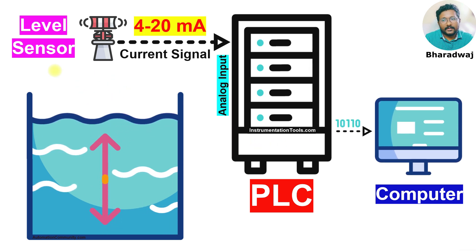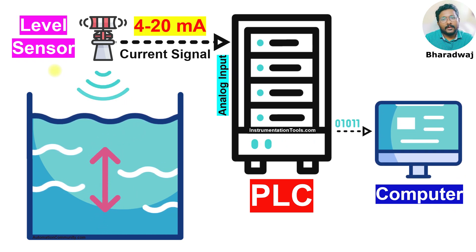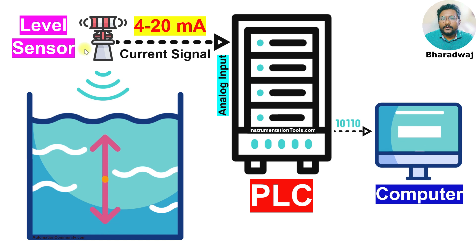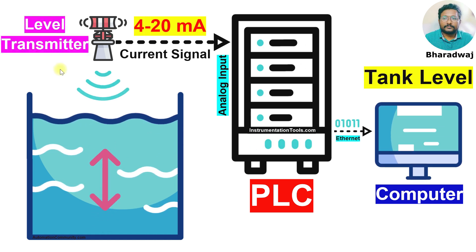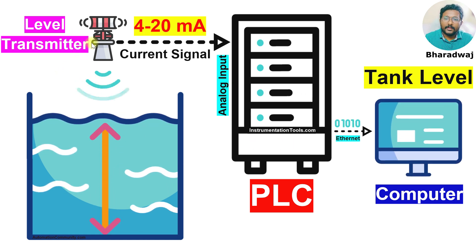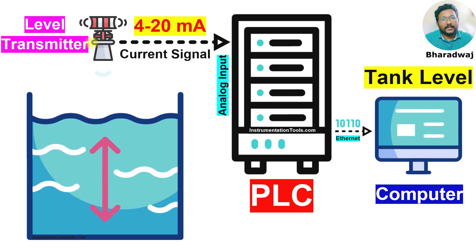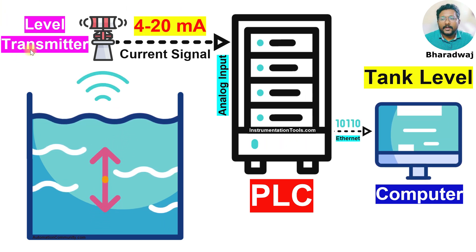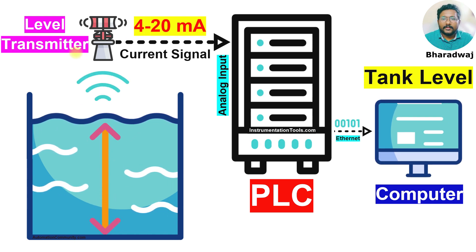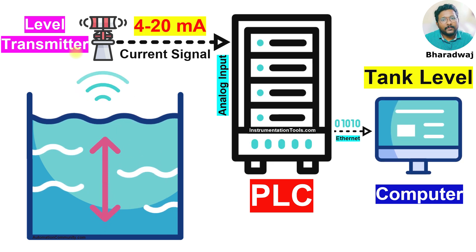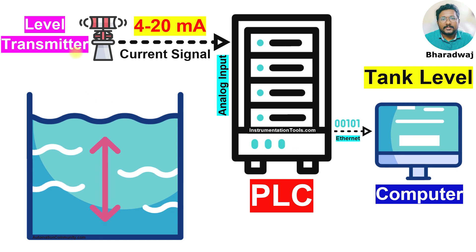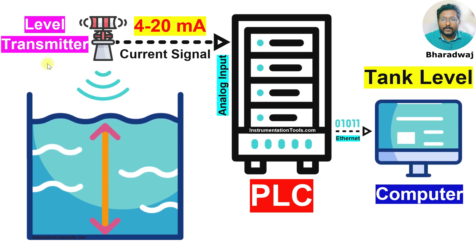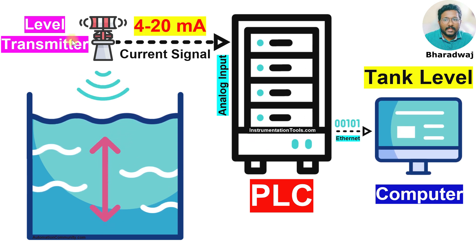In general terminology, we use sensor — like level sensor, pressure sensor, temperature sensor, etc. But in industries, we use level transmitter. The transmitter mostly sends the signal in the form of 4 to 20 mA. That is why we use the word transmitter instead of sensor. A sensor can send the signal in any form, but in industries the standard signal is 4 to 20 mA. For that purpose, the terminology we adopted is level transmitter.